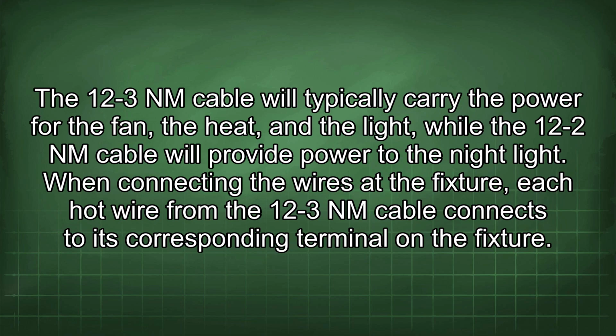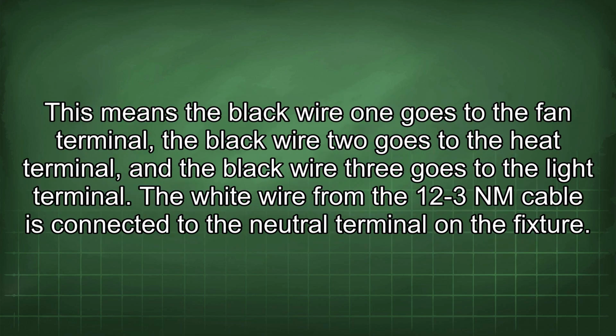When connecting the wires at the fixture, each hot wire from the 12-3 NM cable connects to its corresponding terminal on the fixture. This means the black wire 1 goes to the fan terminal, the black wire 2 goes to the heat terminal, and the black wire 3 goes to the light terminal. The white wire from the 12-3 NM cable is connected to the neutral terminal on the fixture.